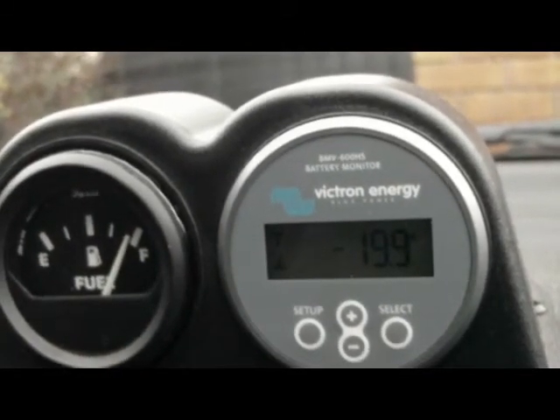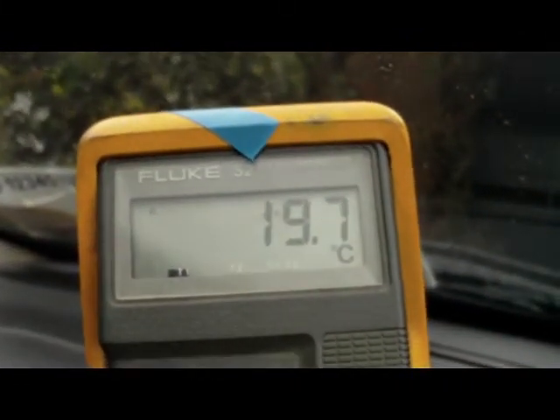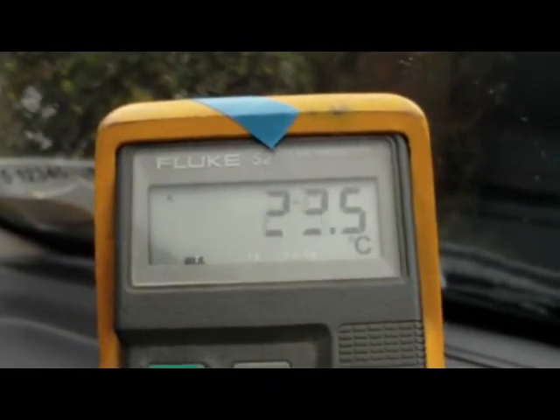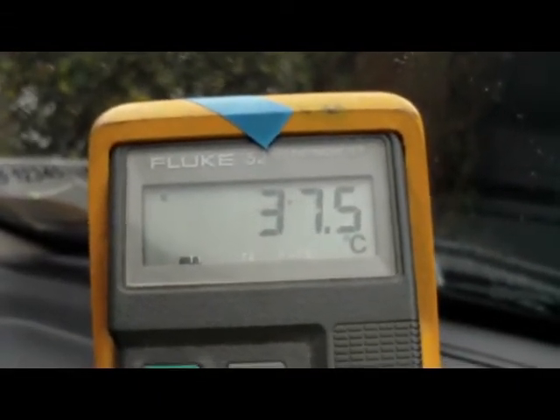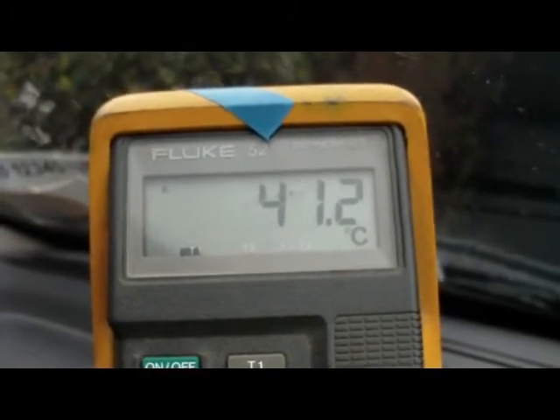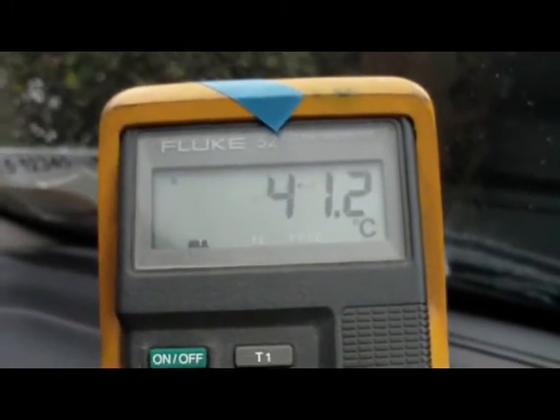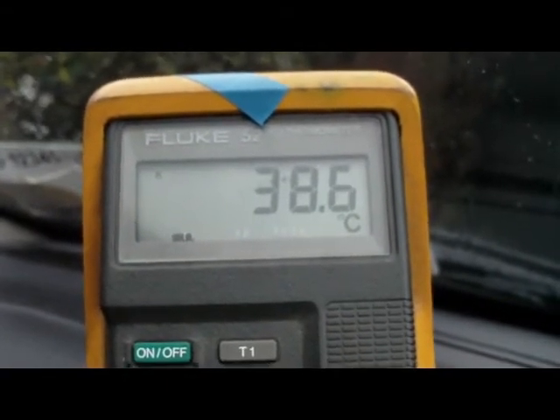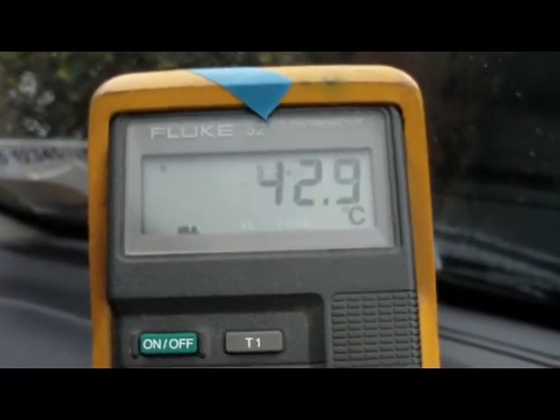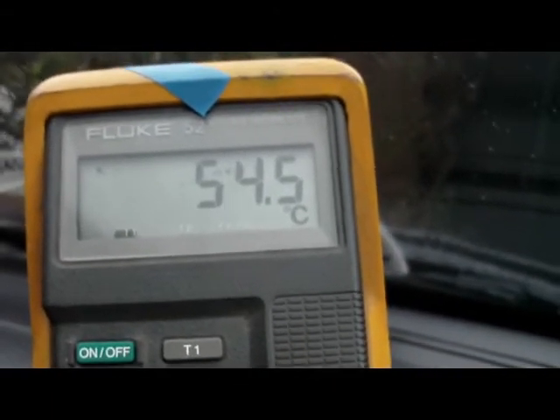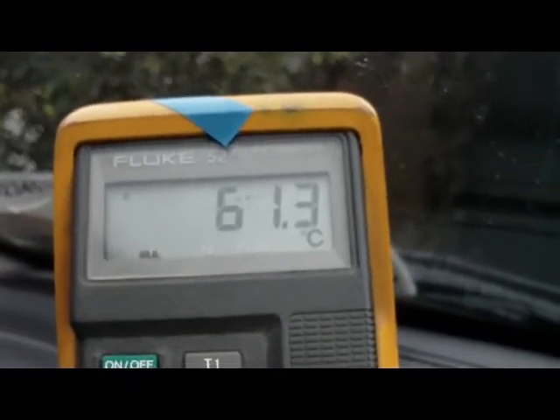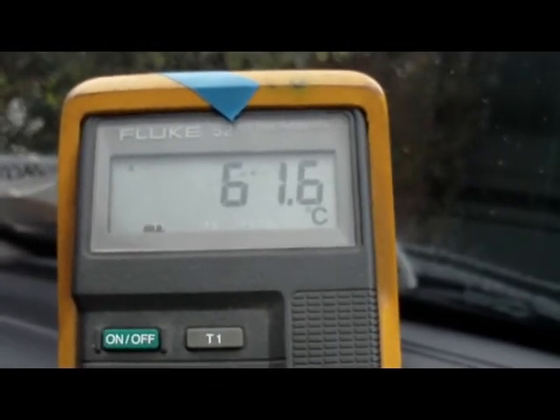I'm going to put the temperature probe here, maybe 6 inches in front of the grill. All grills are turned on here. As we can see, we got near 40 degrees centigrade hot air about 6 inches in front of the grill. If I push the probe just inside the grill, we're practically up over 60 degrees with the probe just sitting in the grill there. Now current has settled down just under 20 amps.